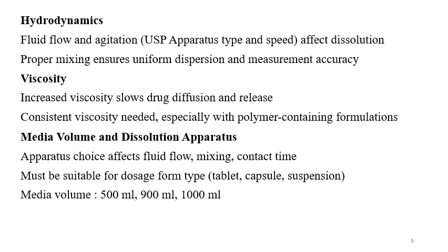Then hydrodynamics. So media should be agitated in the apparatus. Fluid flow and agitation have a great impact onto the dissolution. If you are using basket apparatus or paddle apparatus, then the speed of the basket or the speed of the paddle can affect the hydrodynamics, and hydrodynamics can affect the dissolution. You might have observed coning at low RPM in the paddle apparatus. Proper mixing and proper hydrodynamics ensure uniform dispersion and measurement accuracy.